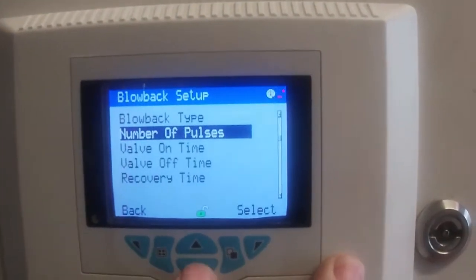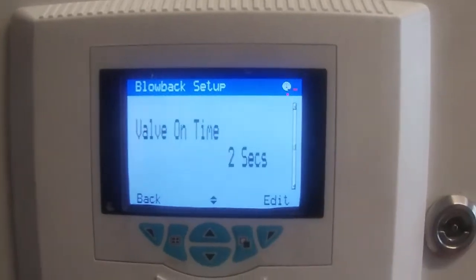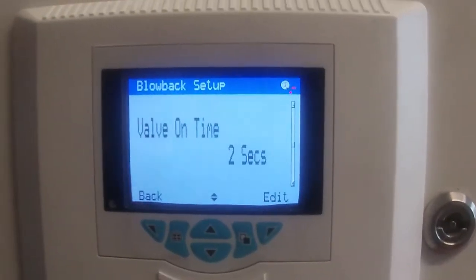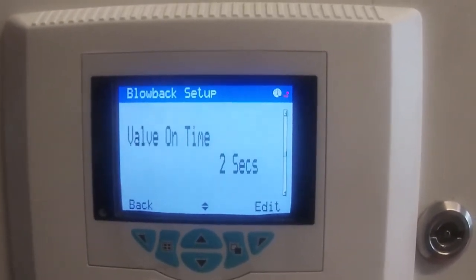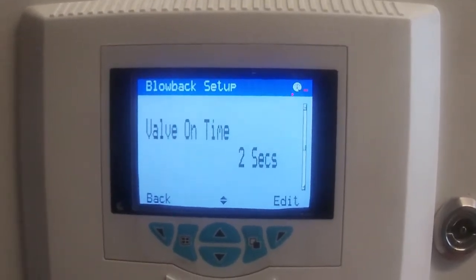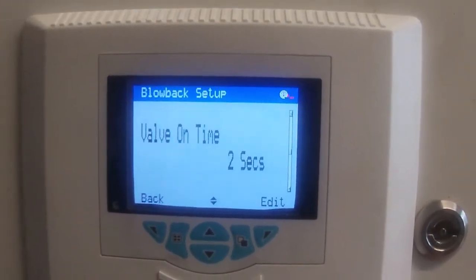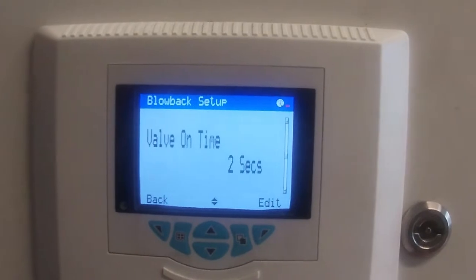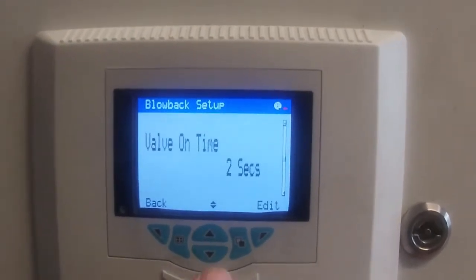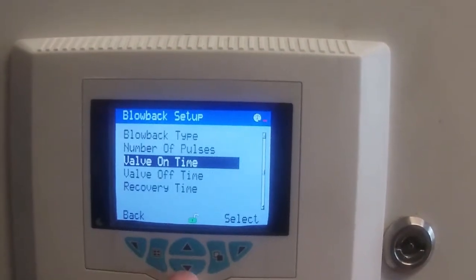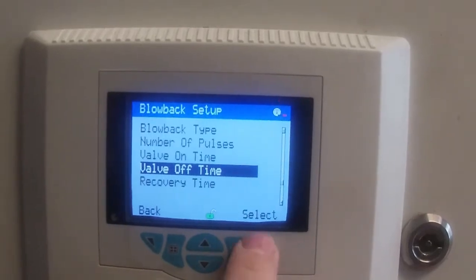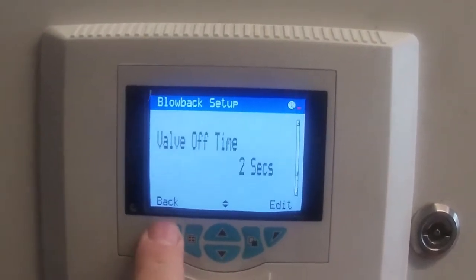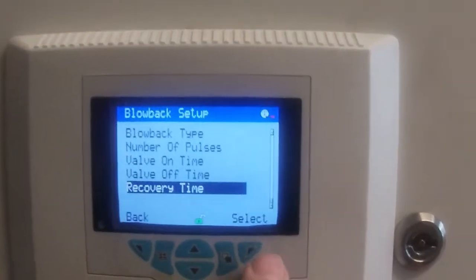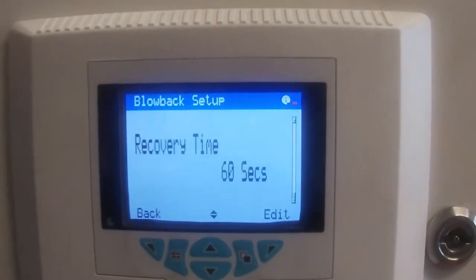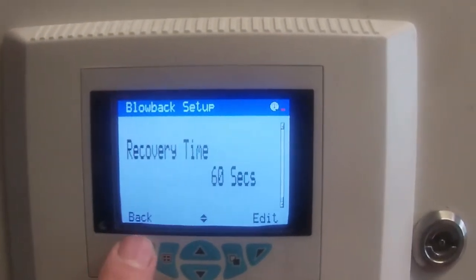Back, amount of time that it should go on, 2 seconds. So it's only a 2-second pulse, but you could set it for whatever you wanted. If it was a really dirty application, you might want to set that for maybe 20 seconds or something like that. Go back, off time, I think I got that set about the same, 2 seconds, back, and recovery time on there, probably again another 60 seconds worth of recovery time.